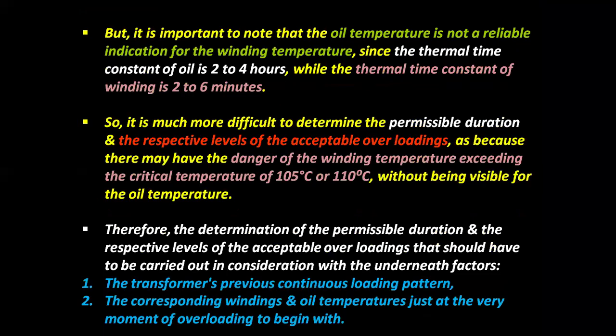But it is important to note that the oil temperature is not a reliable indication of the winding temperature, since the thermal time constant of oil is 2 to 4 hours, while the thermal time constant of winding is 2 to 6 minutes. So it is much more difficult to determine the permissible duration and the respective levels of acceptable overloading, because there may be a danger of the winding temperature exceeding the critical temperature of 105 or 110 degrees centigrade without being visible in the oil temperature.